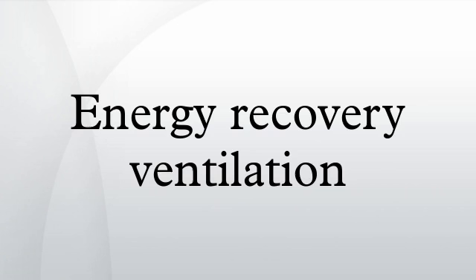Energy recovery ventilation is the energy recovery process of exchanging the energy contained in normally exhausted building or space air and using it to treat the incoming outdoor ventilation air in residential and commercial HVAC systems. During the warmer seasons, the system pre-cools and dehumidifies while humidifying and preheating in the cooler seasons. The benefit of using energy recovery is the ability to meet the ASHRAE ventilation and energy standards, while improving indoor air quality and reducing total HVAC equipment capacity.